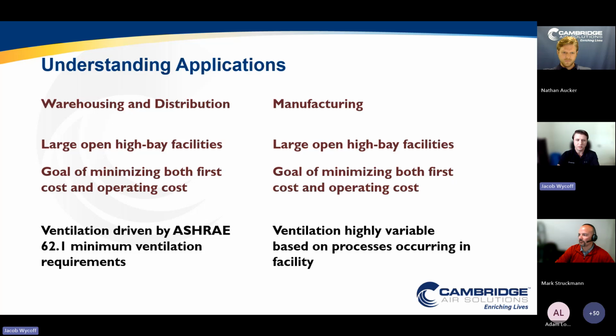The ventilation is pretty much always going to be driven by your ASHRAE 62.1 minimum ventilation requirements or from your LEED building ventilation requirements. Whereas with manufacturing, your ventilation and makeup air requirements are going to be highly variable from building to building, depending on what's happening, what they're producing, what they're doing inside of that facility. So a paint booth is going to be different from a weld shop. It's going to be different from a location where they're manufacturing tires.